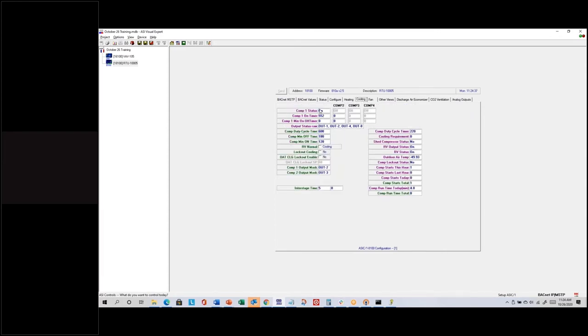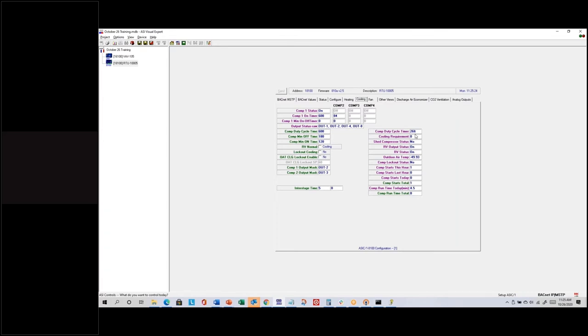Now at 34 percent heating requirement, now 46. I check the compressor operation on the cooling tab — compressor one is almost running the entire duration of 600 seconds. I need to get past 50 percent before I see the second stage run. At 57 percent, compressor two wants to run for the first 84 seconds out of 600. We're further along in the duty cycle than 84 seconds, so compressor two won't run until the duty cycle resets at 600 seconds — another few minutes from now.